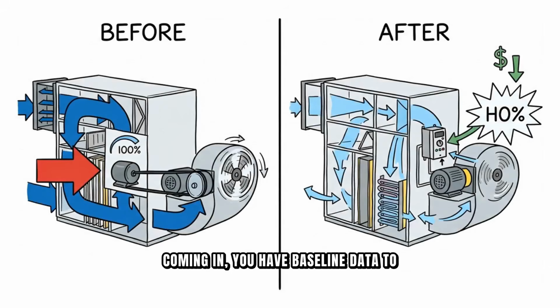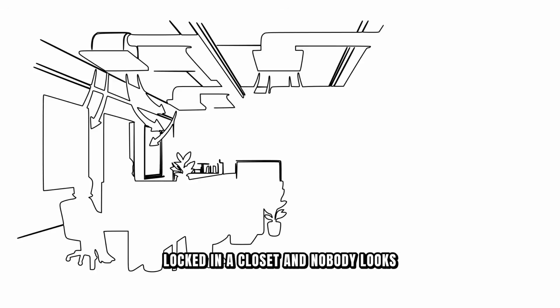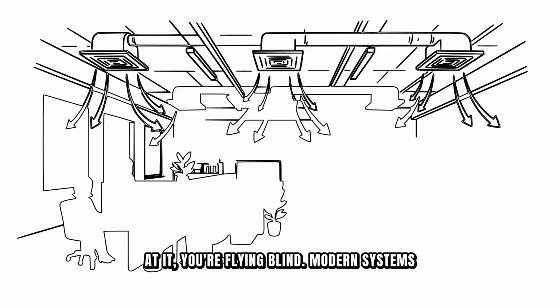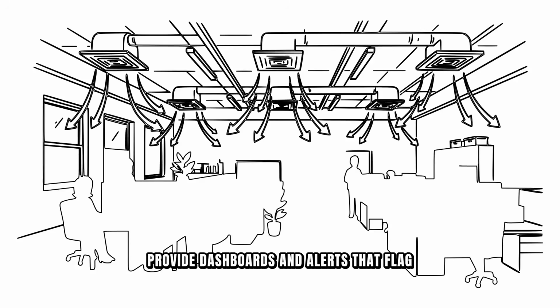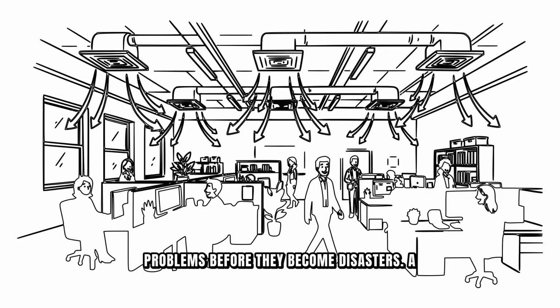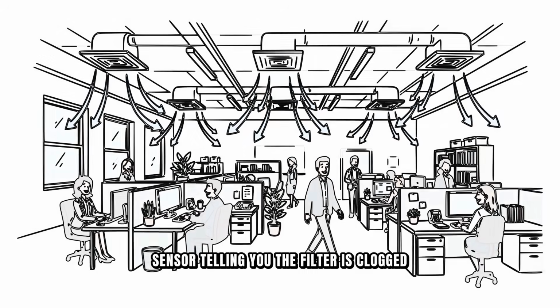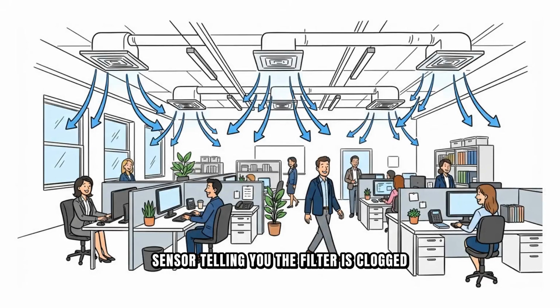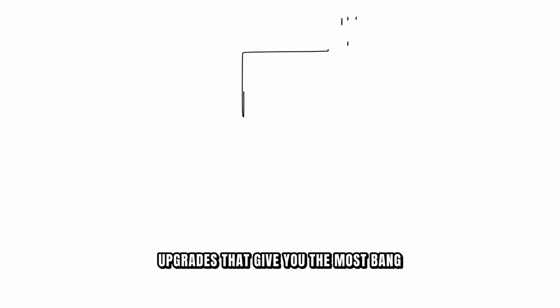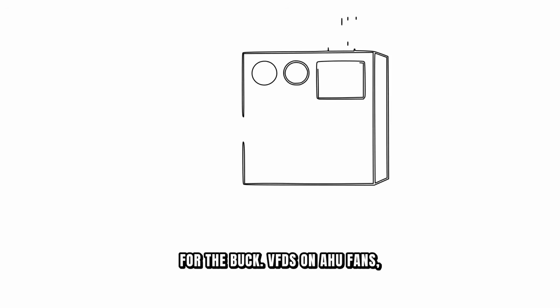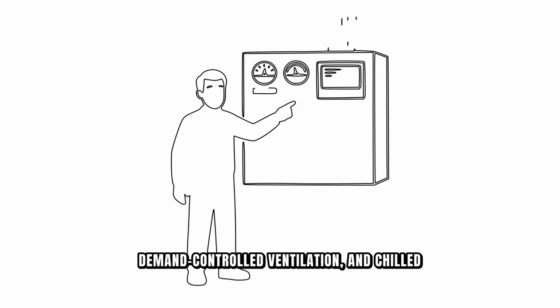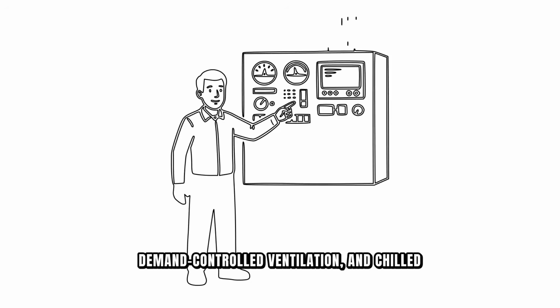If your utility bills spike suddenly or complaints start coming in, you have baseline data to compare against. Third, invest in building automation visibility. If your BAS is locked in a closet and nobody looks at it, you're flying blind. Modern systems provide dashboards and alerts that flag problems before they become disasters. A sensor telling you the filter is clogged is worth its weight in gold compared to the cost of emergency repairs. Fourth, consider upgrades that give you the most bang for the buck.